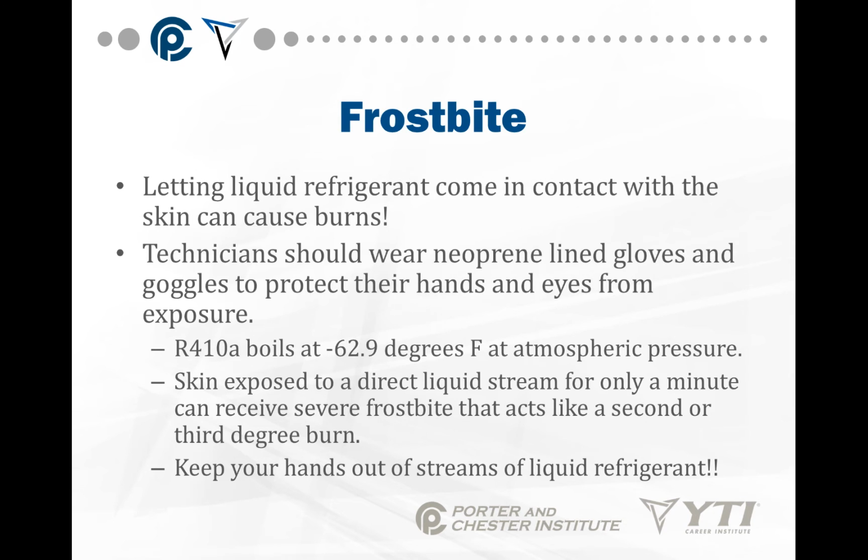Letting liquid refrigerant come in contact with the skin can burn you. Technicians should wear neoprene-lined gloves and goggles to protect their hands and eyes from exposure. R410A, as I said, boils at negative 62.9 degrees Fahrenheit at atmospheric pressure. Skin exposed to this direct liquid stream for only a minute can receive severe frostbite that acts like a second or third degree burn. Keep your hands out of the stream of liquid refrigerants.